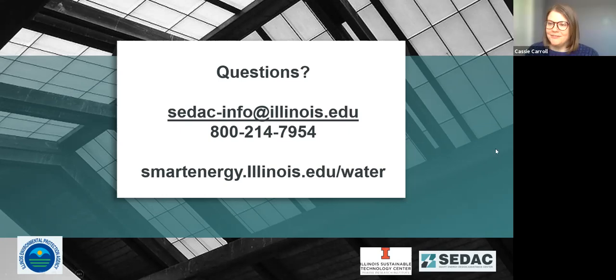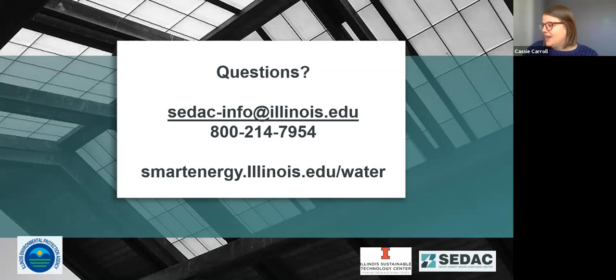Thank you Ryan and Hannah for an awesome presentation. We have a couple of questions. The first: what would indicate that my diffusers are fouling? As diffusers foul, that's going to increase the system pressures. So one method is to watch system pressures and system flow — if you see pressures rising versus your flow, that will indicate fouling and may also provide some indication of when it's time to clean.